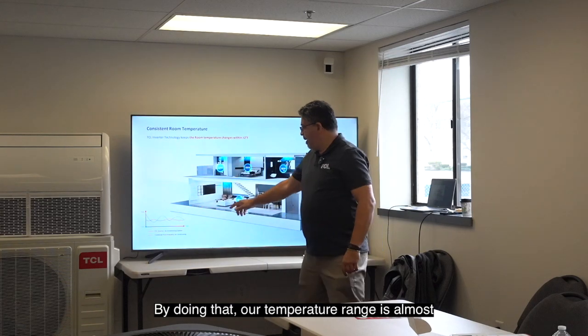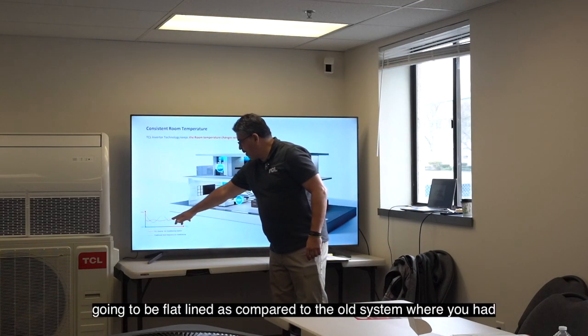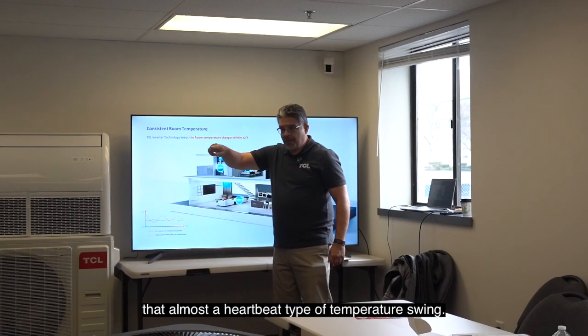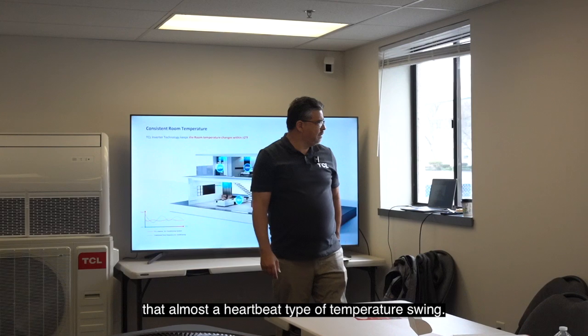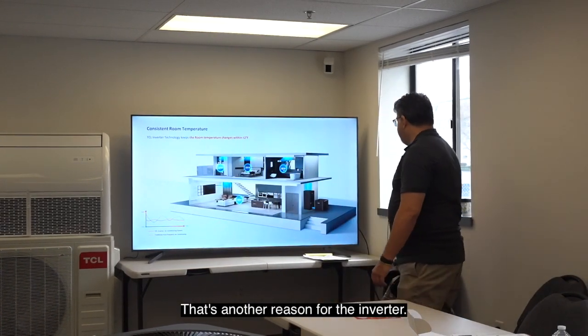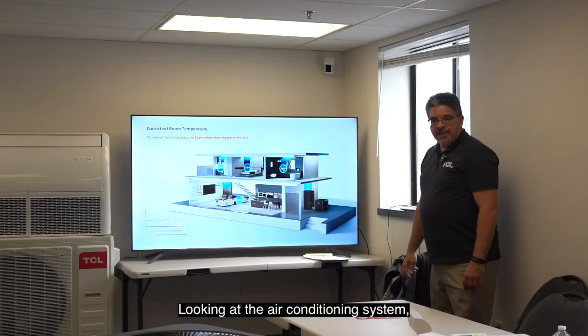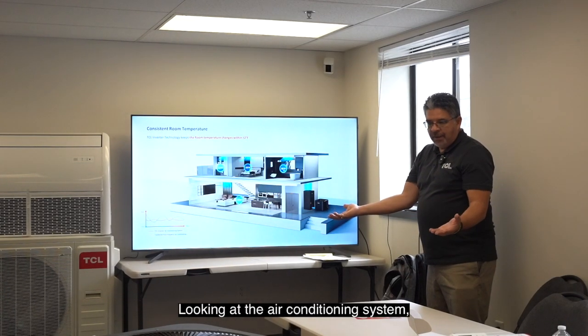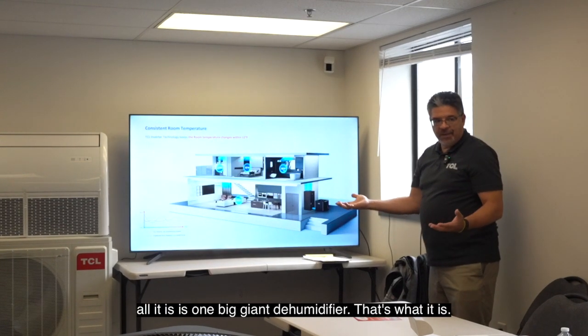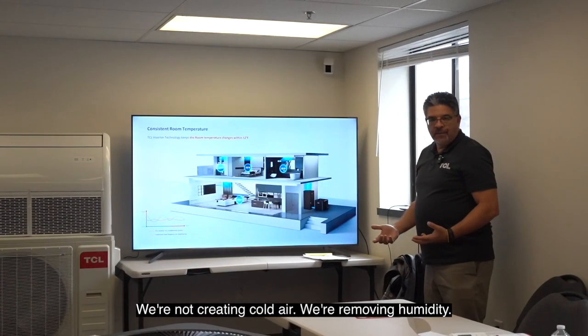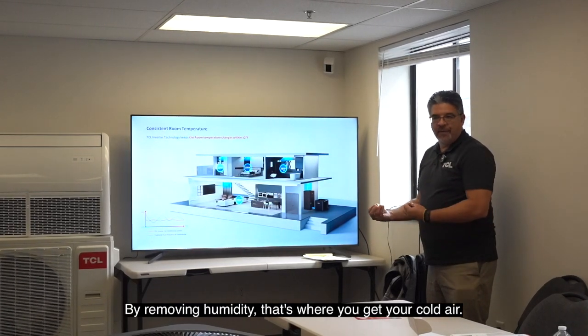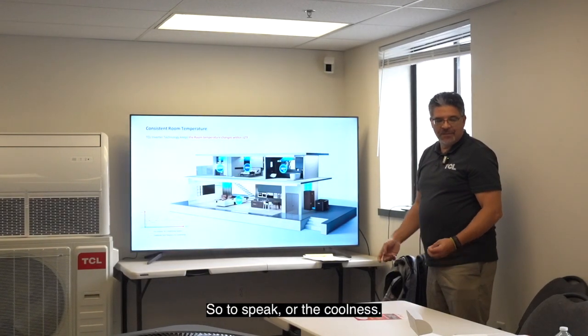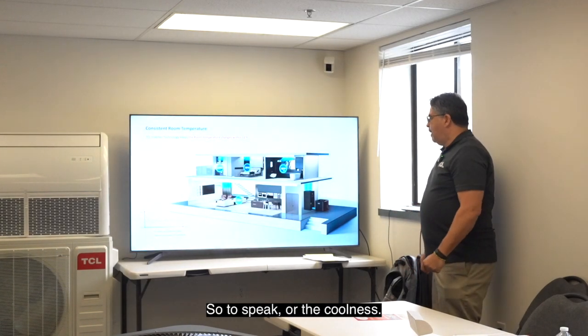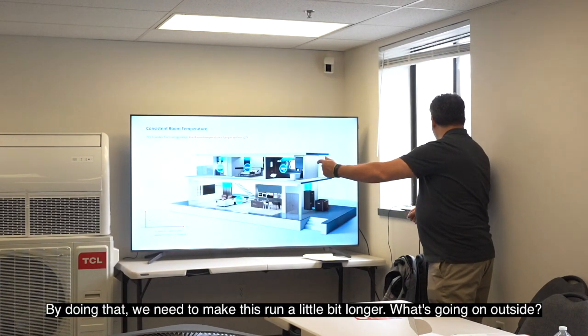And by doing that, our temperature range is almost going to be flatlined as compared to the old system where you had that almost a heartbeat type of temperature swing. That's another reason for the inverter. If you look at the air conditioning system, it is one big giant dehumidifier. That's what it is. We're not creating cold air. We're removing humidity, and by removing humidity, that's where you get your cold air, so to speak, or the coolness. By doing that, we need to make this run a little bit longer.